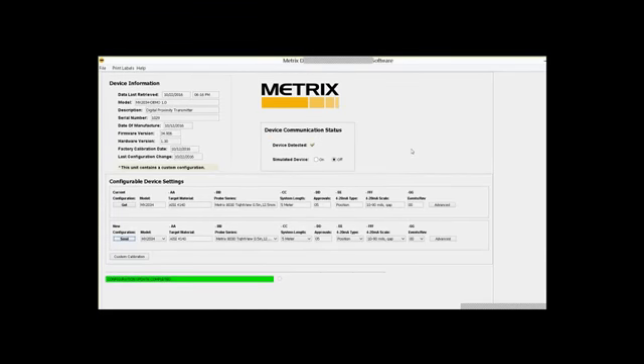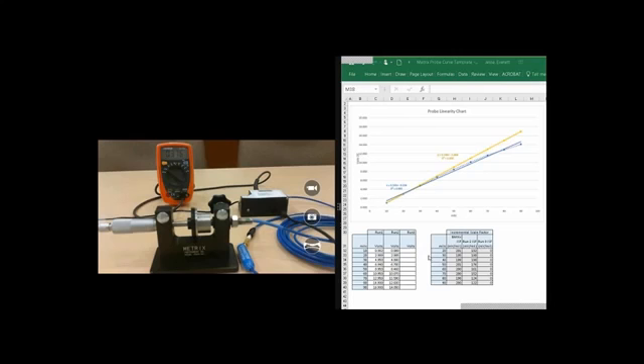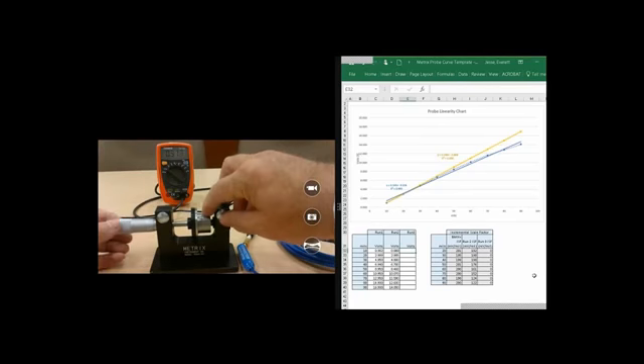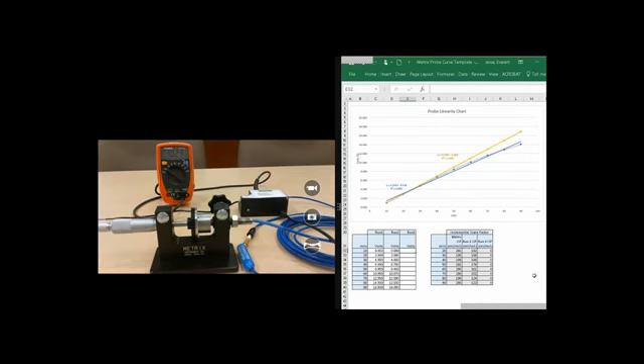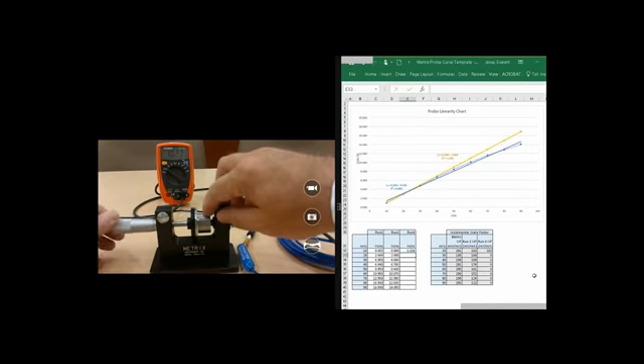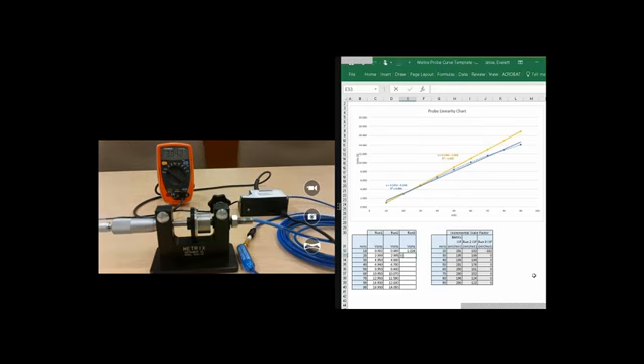With the new TightView configuration loaded, we are able to rerun the calibration check to physically see if the new configuration was successful. As before, we will record DC voltages in 10 mil increments. When we adjust the micrometer in 10 mil gap voltage increments from 10 mils to 90 mils, you will notice that the line created by the points is now straight. You will also notice that the incremental scale factor is between 190 and 210 millivolts per mil.